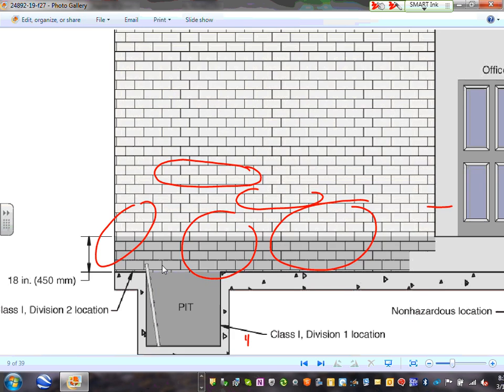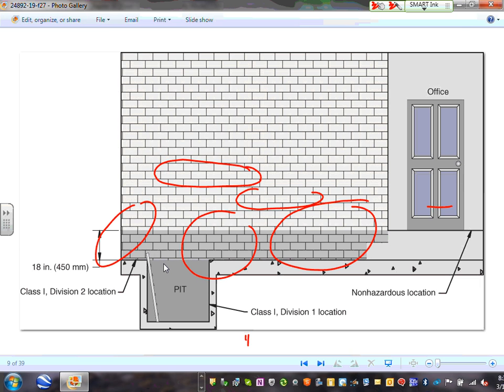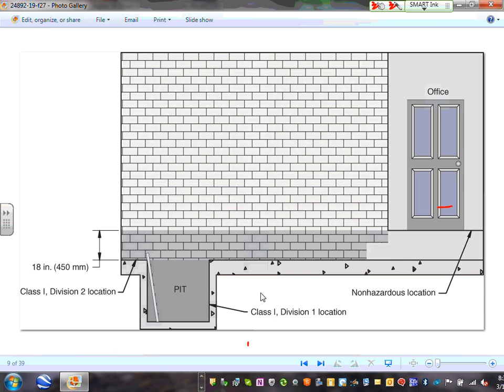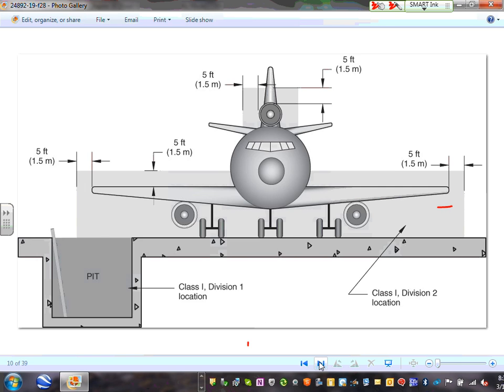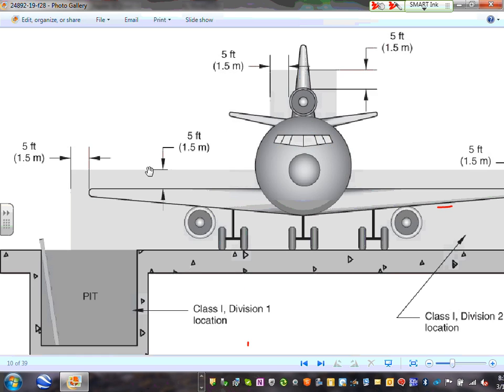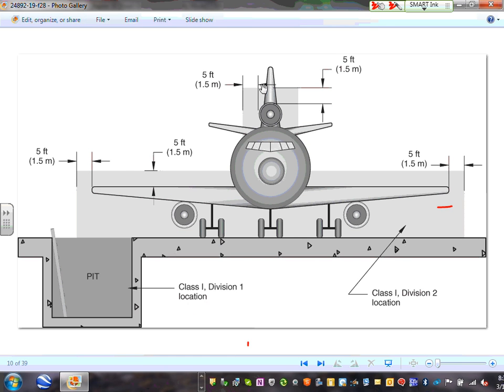We talked about, guys, the pit in a commercial garage, and we said it's class 1 div 1, up to 18 inches. Up to 18 inches, Derek, right here. I don't know if you guys can see right here, up to 18 inches, class 1 div 2. Aircraft hangars, around the aircraft hangar, 5 feet. Can you guys see 5 feet from the wings all the way 5 feet above the wing, 5 feet above the engine, in all directions, class 1 div 2. And the pit is a class 1 div 1.